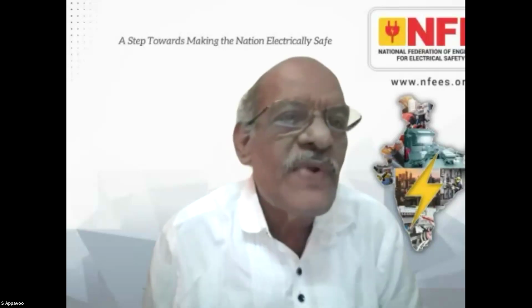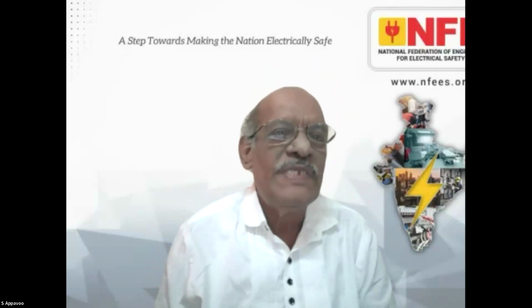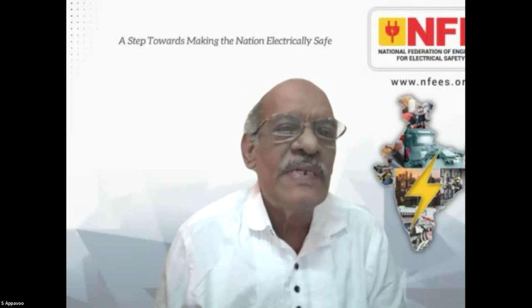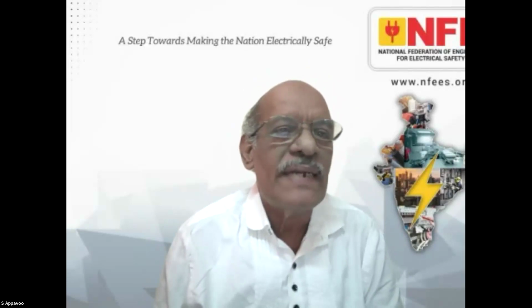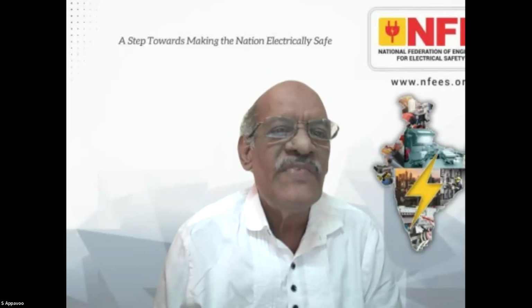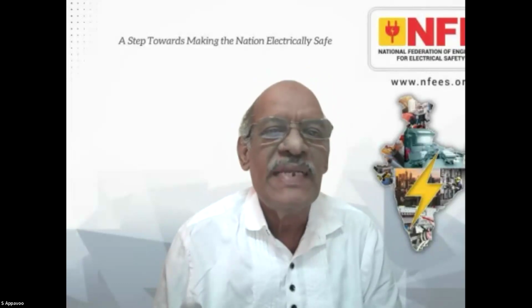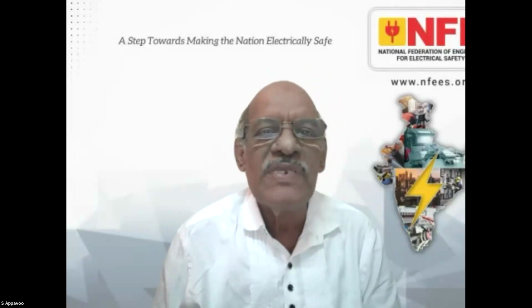There's a question from Mr. Balu G: is an earth pit necessary for every down conductor? For example, if there are 10 down conductors in a building, can we provide 5 earth pits after connecting them to the ground? No — for a type A earthing with an earth pit, if you have 10 down conductors, you are 100% required to have 10 earth pits. That is mandatory.